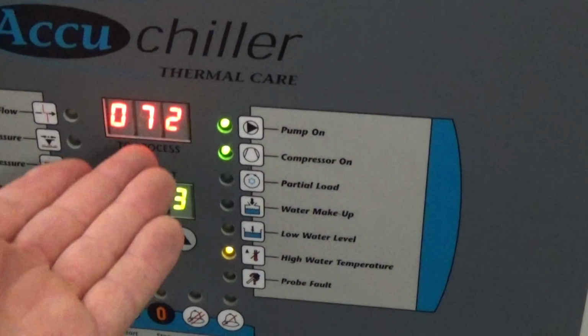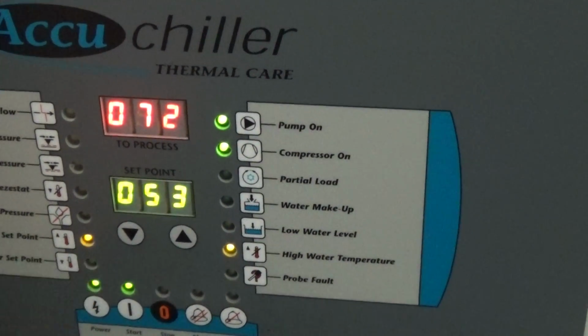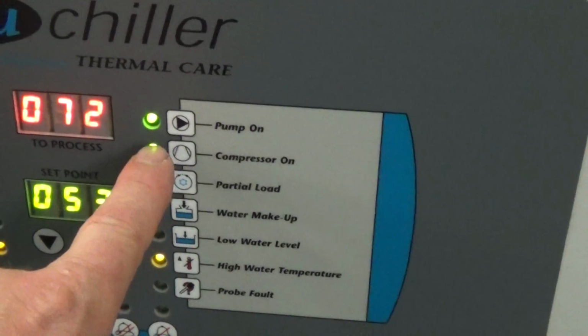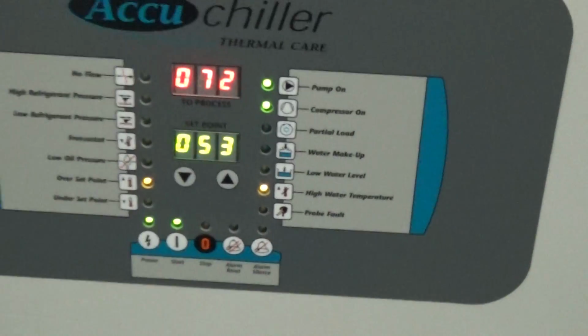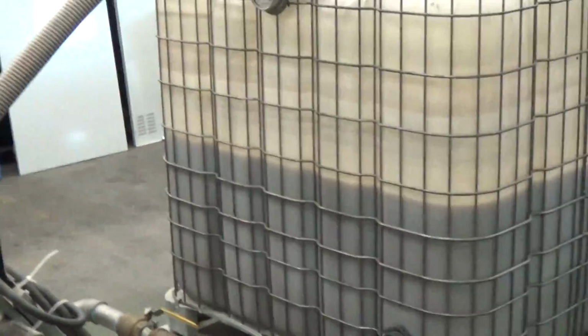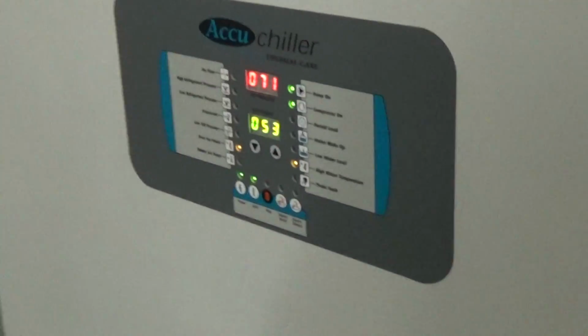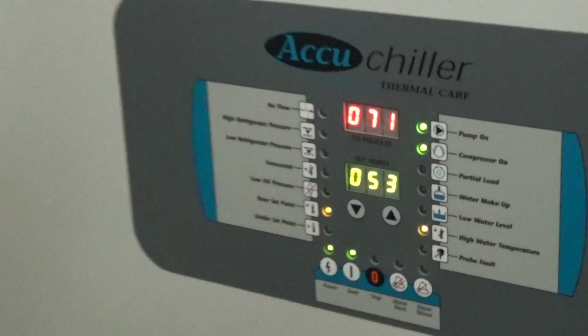In this case here, because we have the water kind of high, you'll see it'll say over set point and high water temperature, but our indicator lights show compressor on and pump on. Now we have probably 130, 140 gallons of fluid in our test tank, so it'll take a little while to start cooling that down substantially. You can see we're starting to cool down a little bit already. What we're going to do here is on my on delay. Oh, it just kicked in. I think it was like a minute or two. So now both compressors are on. That's your compressor number 2 contactor.